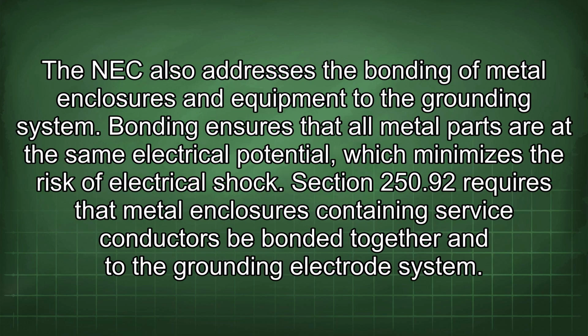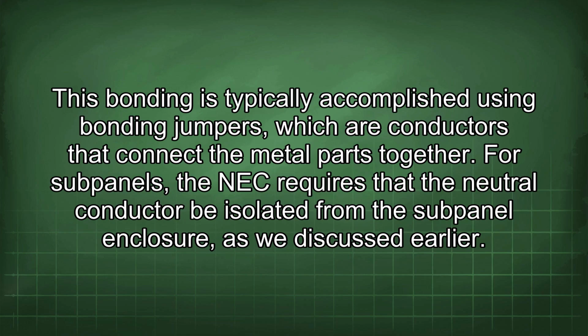The NEC also addresses the bonding of metal enclosures and equipment to the grounding system. Bonding ensures that all metal parts are at the same electrical potential, which minimizes the risk of electrical shock. Section 250.92 requires that metal enclosures containing service conductors be bonded together and to the grounding electrode system. This bonding is typically accomplished using bonding jumpers, which are conductors that connect the metal parts together.